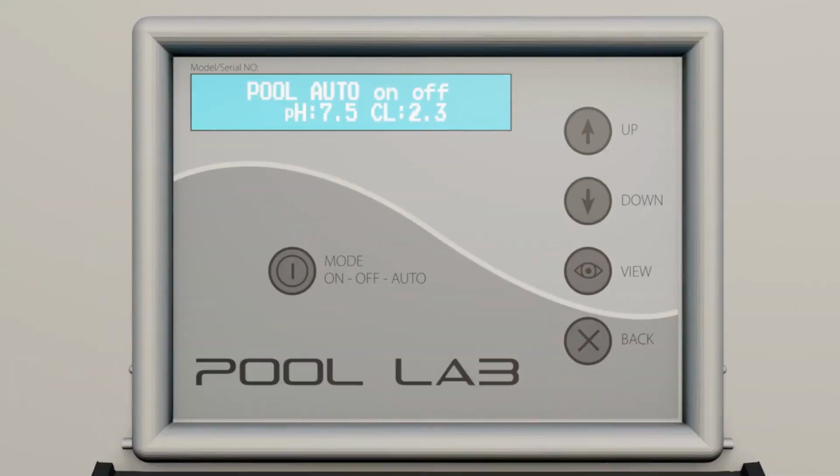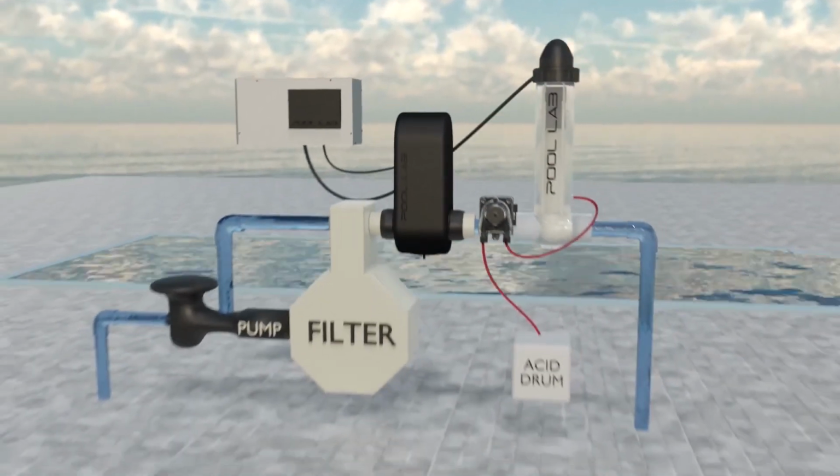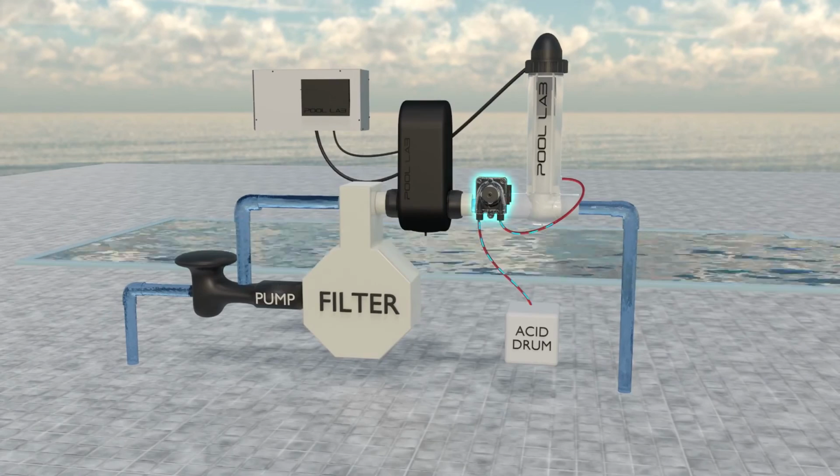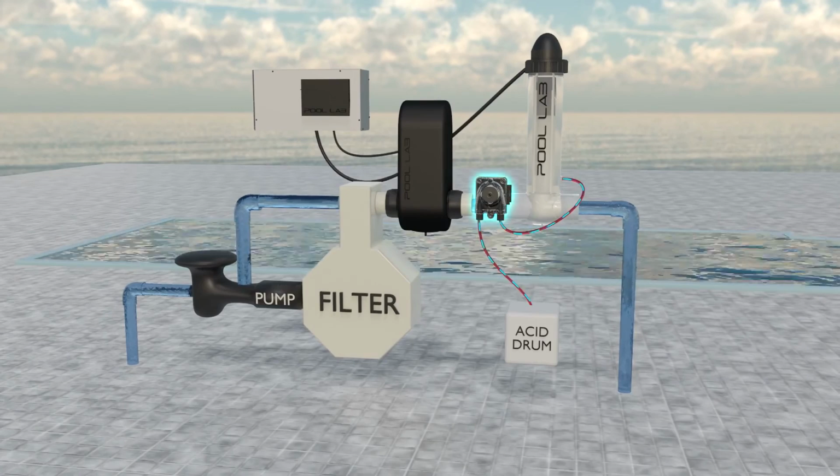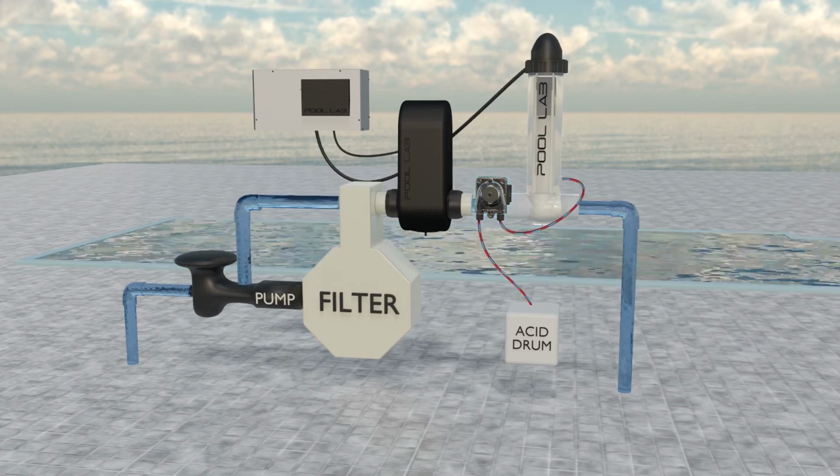Algorithms calculate the pool's requirements and automatically adjust dosing to maintain chlorine and pH targets. Chlorine and acid feed history can also be viewed. If pH adjustment is required, the peristaltic pump is initiated to feed acid. When chlorine production is required, cell power is activated.